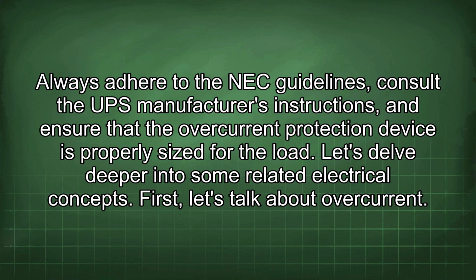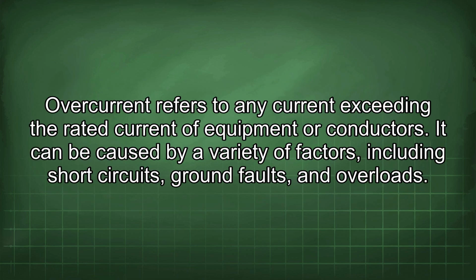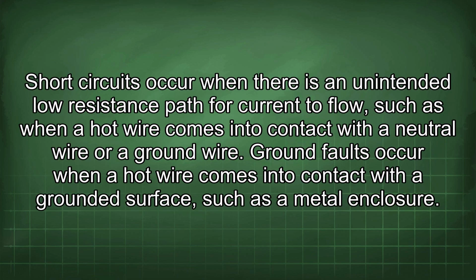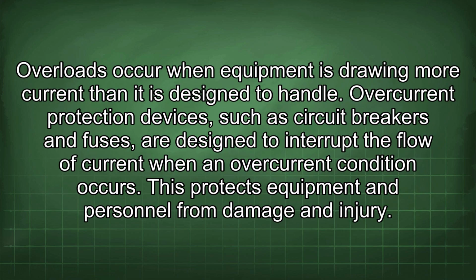First, let's talk about overcurrent. Overcurrent refers to any current exceeding the rated current of equipment or conductors. It can be caused by a variety of factors, including short circuits, ground faults, and overloads. Short circuits occur when there is an unintended low resistance path for current to flow, such as when a hot wire comes into contact with a neutral wire or a ground wire. Ground faults occur when a hot wire comes into contact with a grounded surface, such as a metal enclosure. Overloads occur when equipment is drawing more current than it is designed to handle.